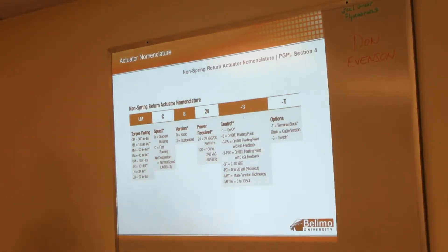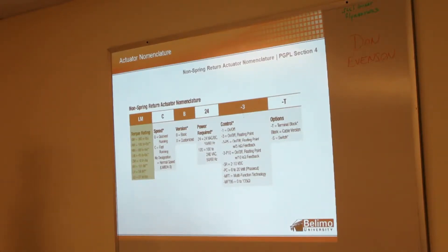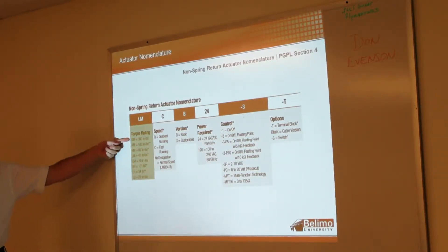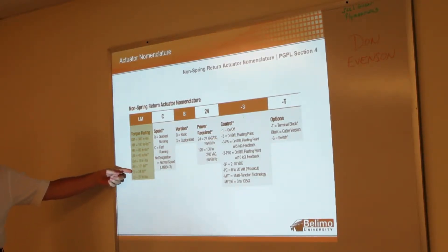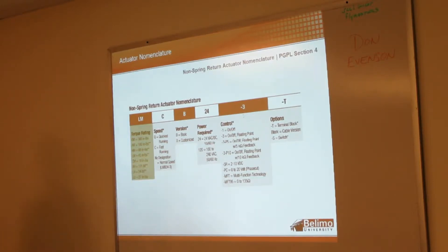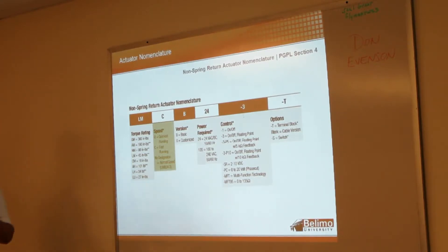For non-spring, we have the same setup. So we have the LM - M just means motor - and we run from 360 inch-pounds down to 18 inch-pounds. And then we have a couple linear and one rotary style actuator as well.